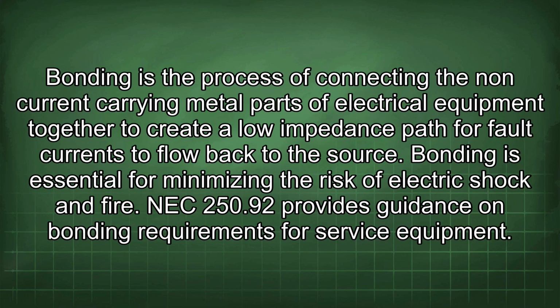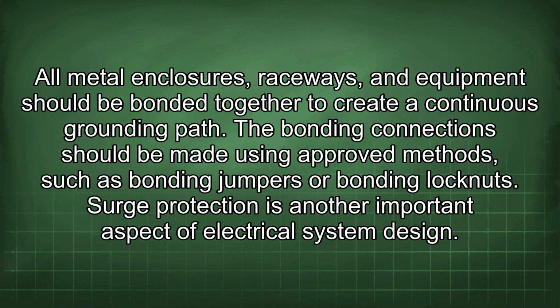Bonding is the process of connecting the non-current carrying metal parts of electrical equipment together to create a lower impedance path for fault currents to flow back to the source. Bonding is essential for minimizing the risk of electric shock and fire. NEC 250.92 provides guidance on bonding requirements for service equipment. All metal enclosures, raceways, and equipment should be bonded together to create a continuous grounding path. The bonding connections should be made using approved methods, such as bonding jumpers or bonding lock nuts. Surge protection is another important aspect of electrical system design.